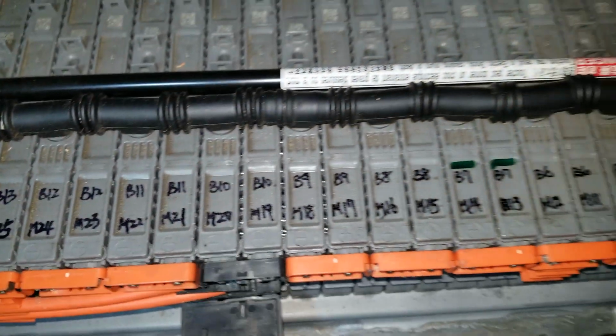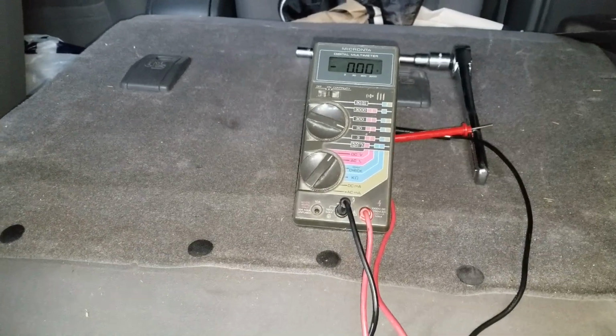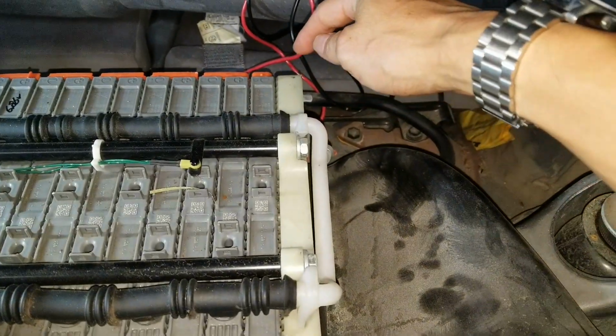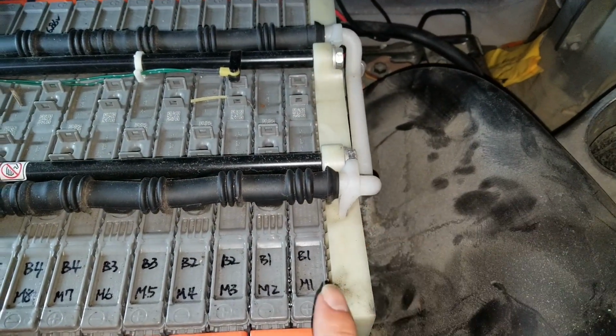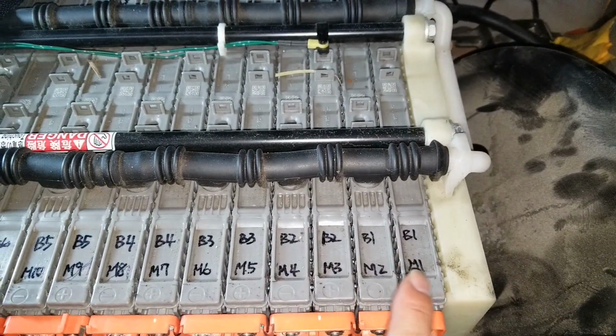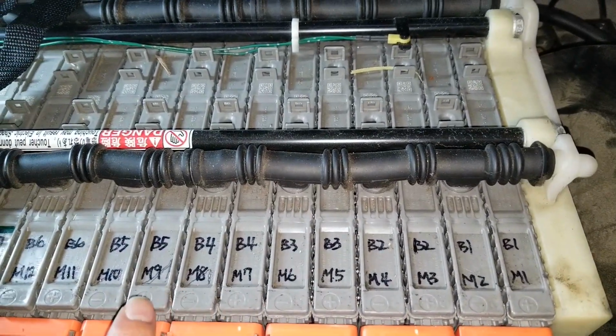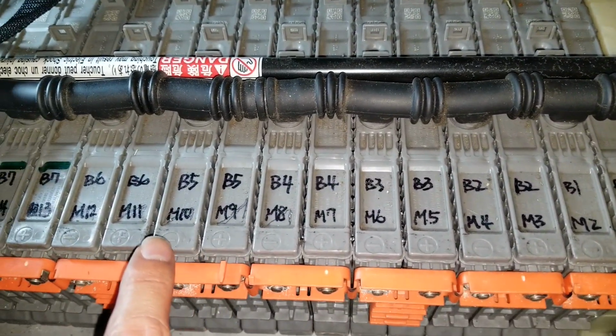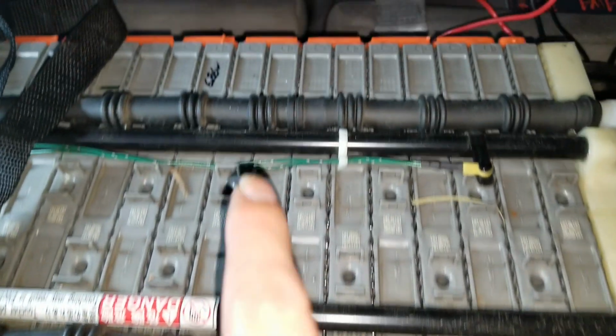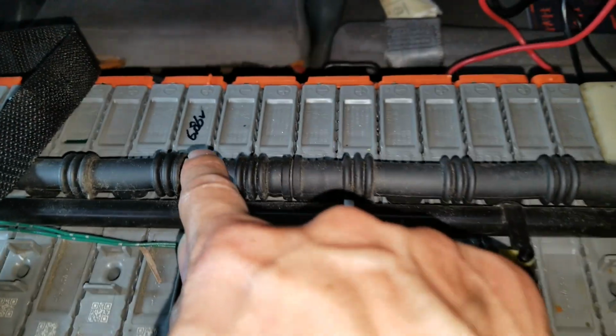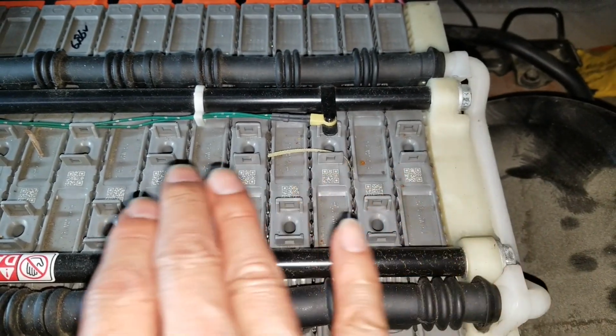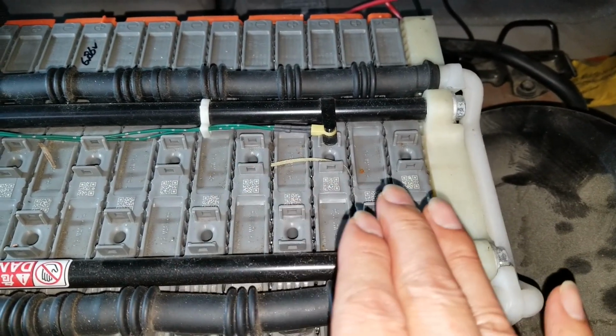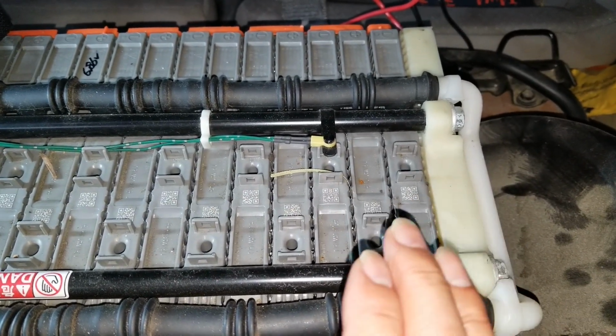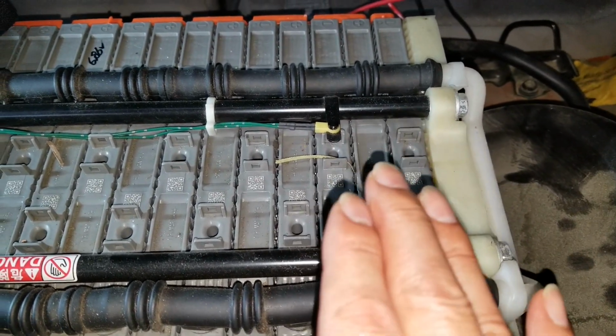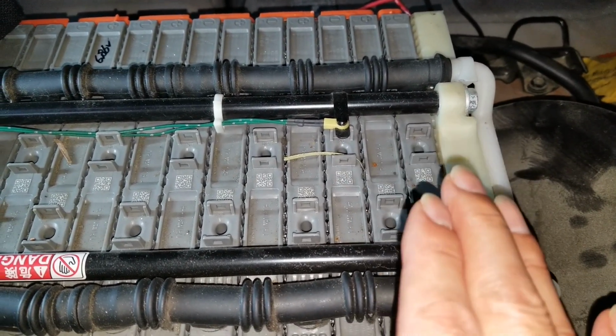Okay, so I use my voltmeter to measure the voltage across each module. So far all these are good, module all the way to module 9. Somehow with module 10 I'm only getting like 6.86 volts, which is not good. That's very low. Other modules are at least 8.1 or 8 volts, or sometimes 7.9 or 7.8. Anything above 7.8 is good.